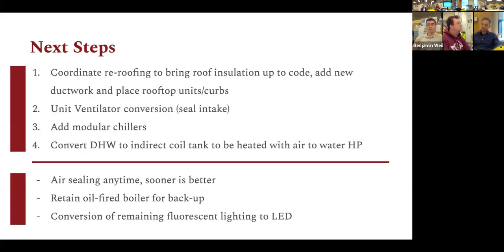So as to the order in which these upgrades could happen, the first step would probably be to coordinate the re-roofing, which you had mentioned was already in the plan for the near future. That would include bringing the roof up to code, probably adding another layer of foam. And then while that's happening, we would propose adding roof curbs and making holes in the roof basically for where the new ductwork would be coming up through. Step number two would be, after those rooftop units get placed, convert the unit ventilators to fan coils, which just means sealing off the fresh air intake. And that could be actually done separately because, in the meantime, we could just turn the fresh air dampers off after those rooftop units are placed.